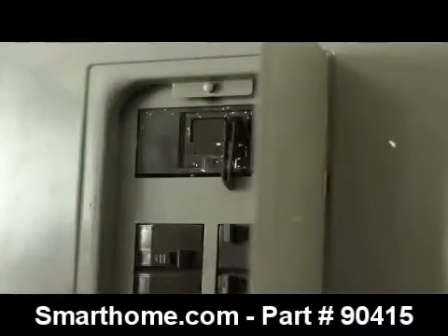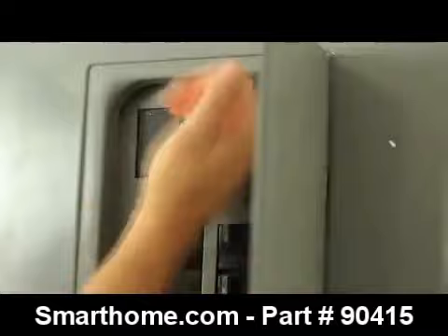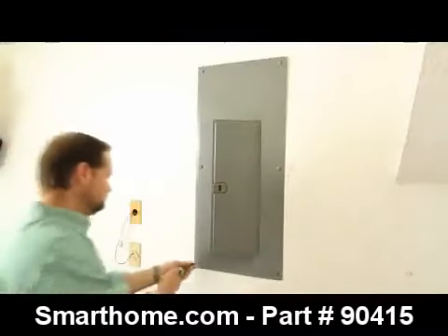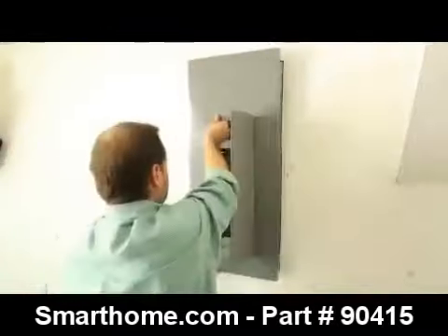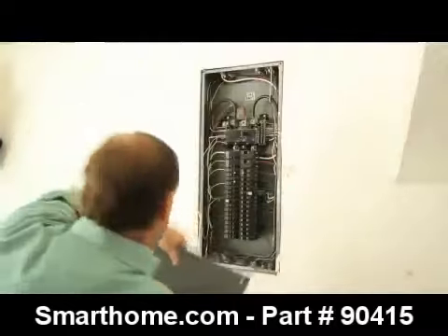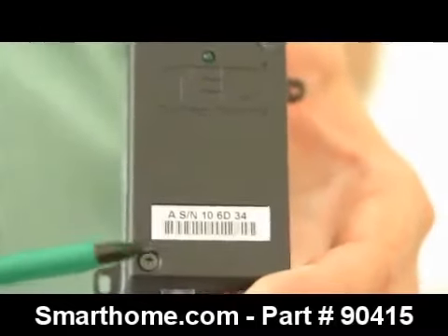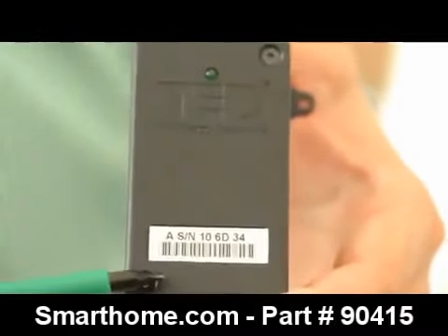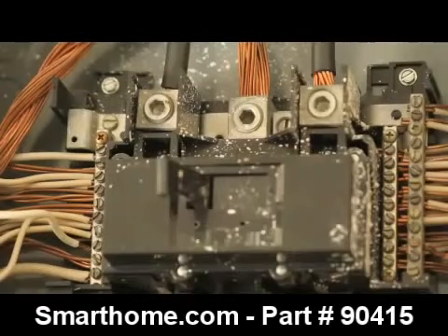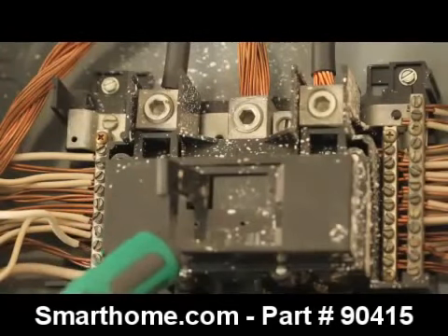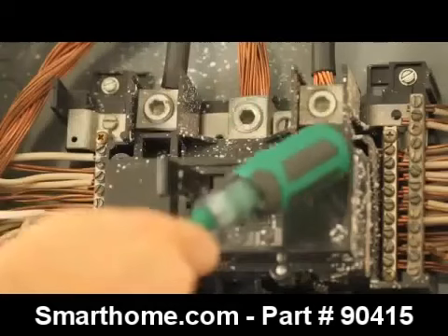Thanks, Melissa. The first step is to turn off all power to the circuit breaker panel by turning off the main breaker or main switch. The second step is to remove the circuit breaker panel cover. Before installing the MTU, note the 6-digit ID number, as you will need to know this number when setting up your software.